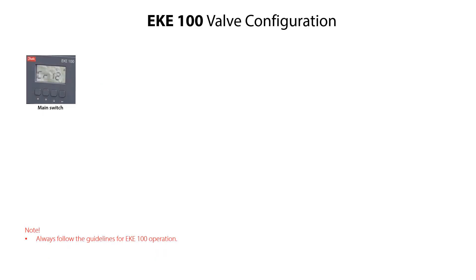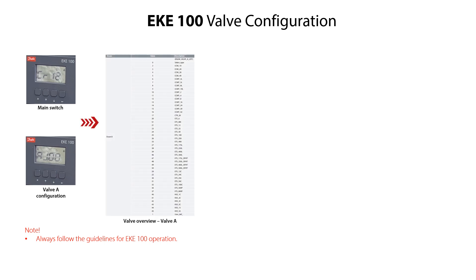To do an EKE100 valve A configuration by selecting a suitable stepper motor valve, from the main switch CR12 mode, press the arrow down key several times to access the valve A configuration, specified as AJ00. Press the enter key to access the available valves. You can see the different suitable valves and related values in the overview shown here. Press the arrow up or arrow down keys to find and select a suitable valve, then press the enter key to confirm and return to the AJ00 mode. Once valve A is selected, press the arrow up key to return to the CR12 mode.